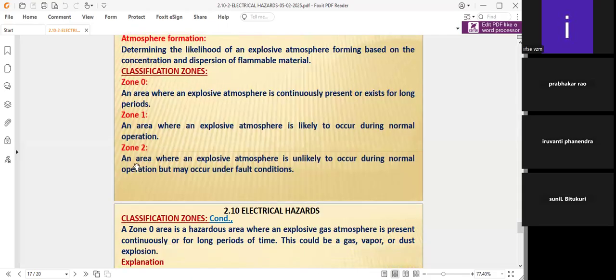Coming to zone 2 areas: an area where an explosive atmosphere is unlikely to occur during normal operation but may occur under fault conditions. See, there is a difference here. Likely to occur during normal operation, versus unlikely to occur during normal operation but may occur under fault conditions. If there is any human error, circuit error, or malfunction of the electrical functions, it will be treated as a zone 2 area.